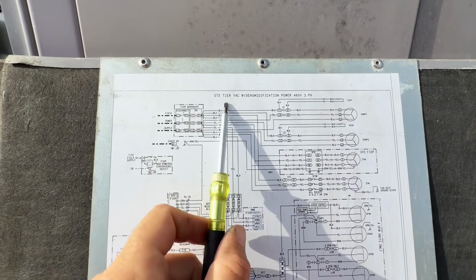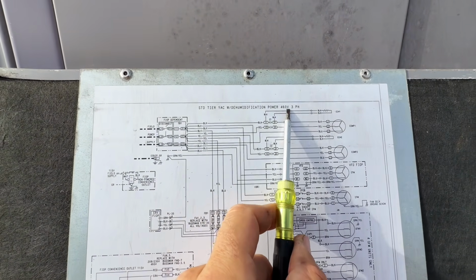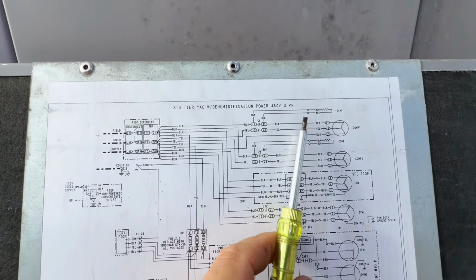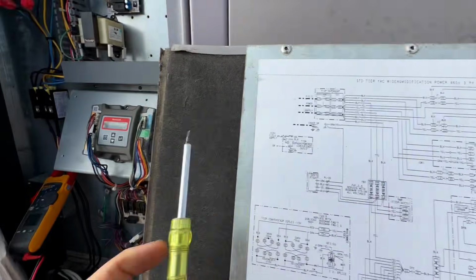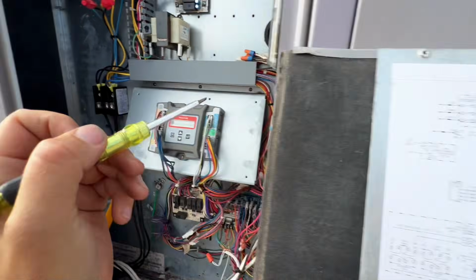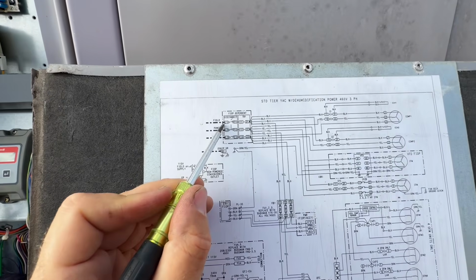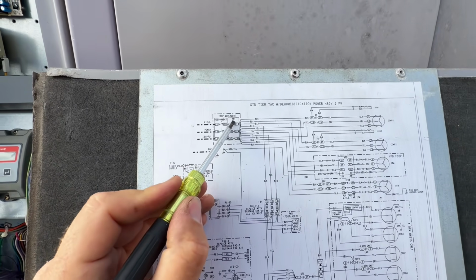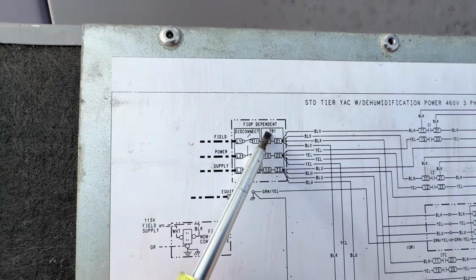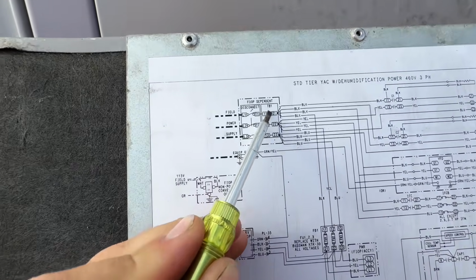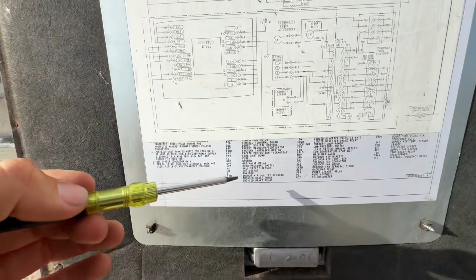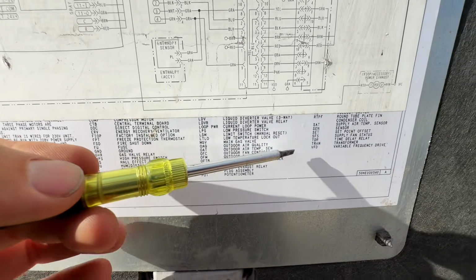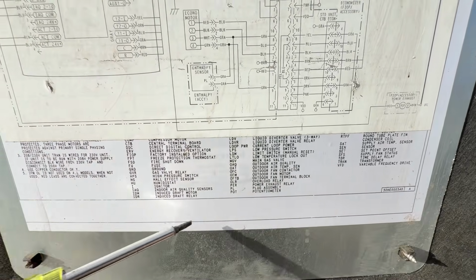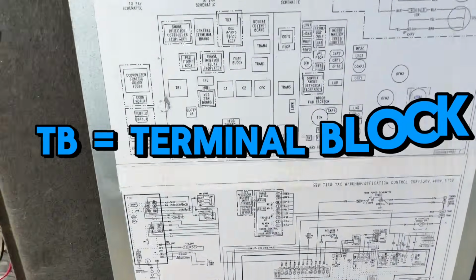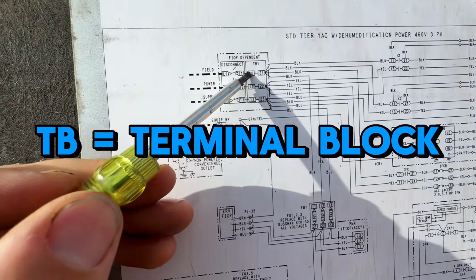So this is our main power, 460 volts 3-phase, and that's what I'm looking for because this is our main power coming in. So I can see over here we have our disconnect. This is our terminal block 1. If you're ever confused about what something means, you can simply go here, and then usually down there you have a legend, and this is probably covered or something, but TB is terminal block, so you can know that.